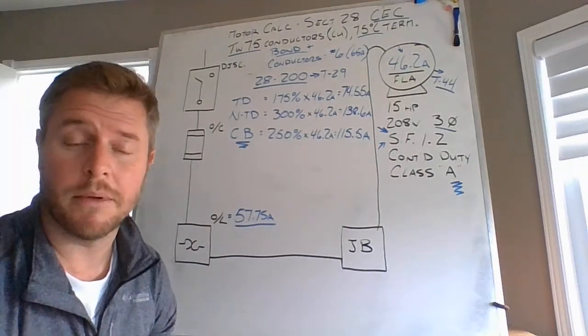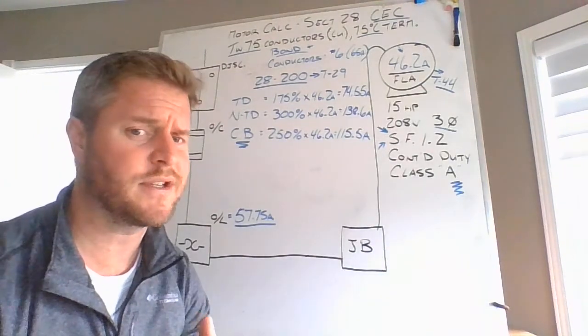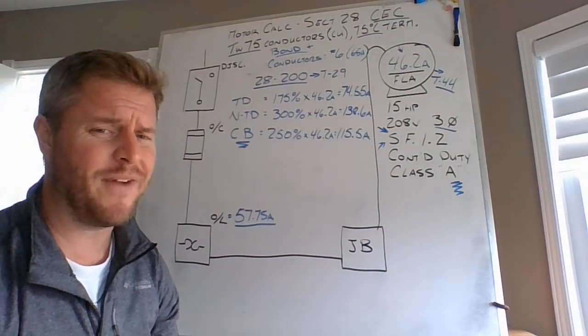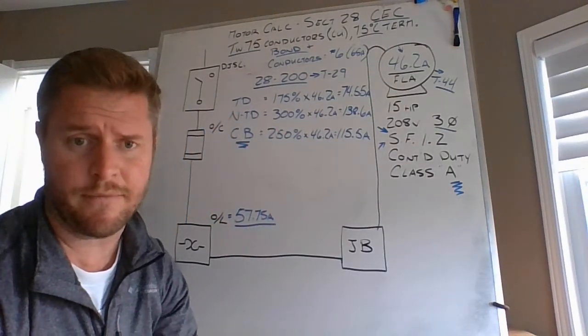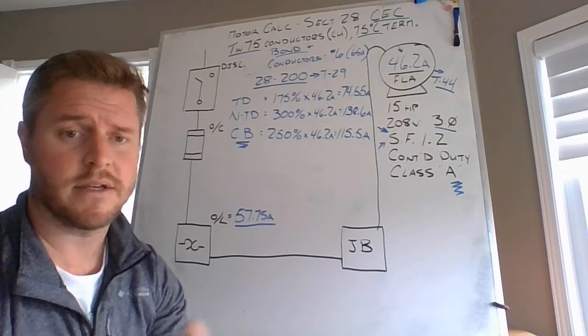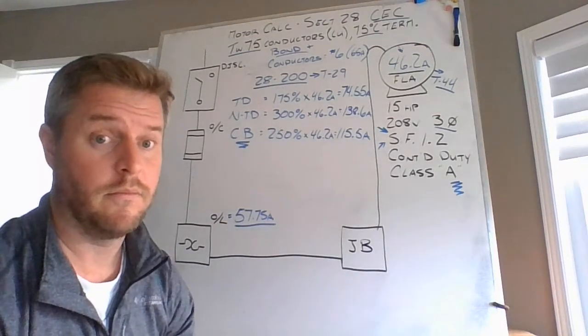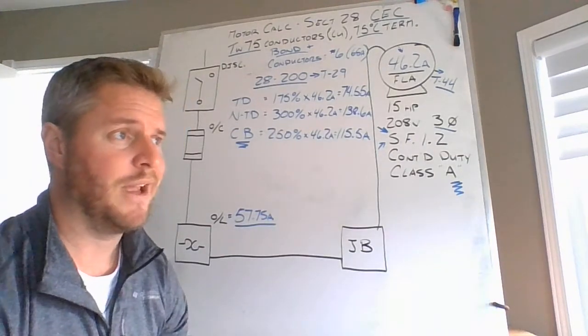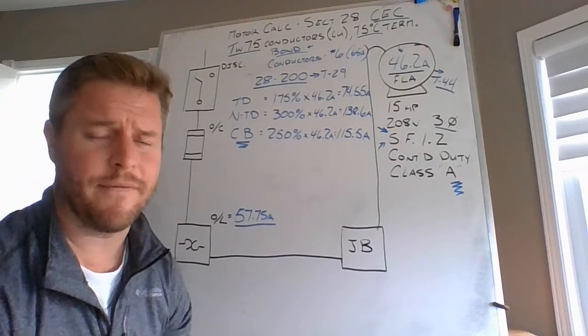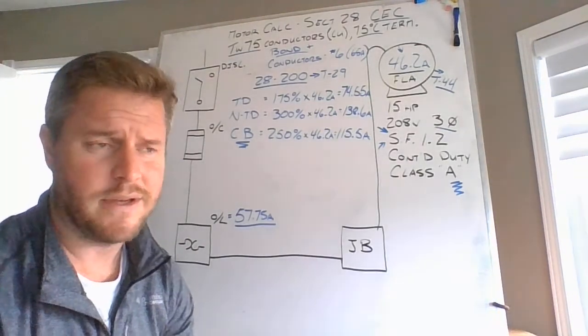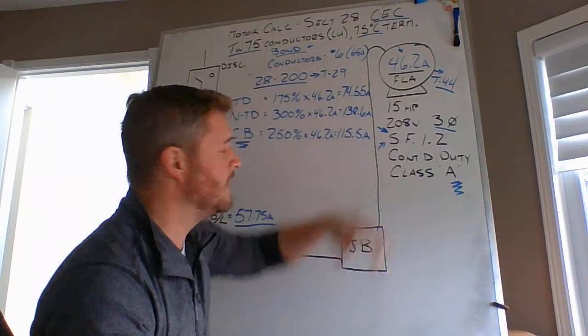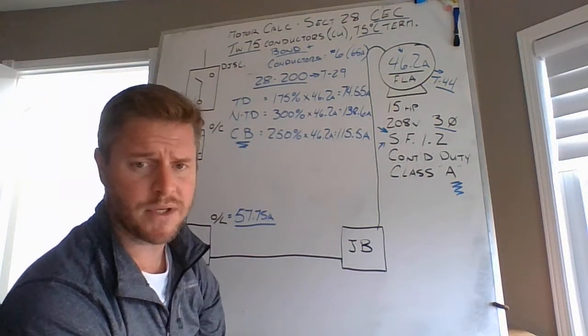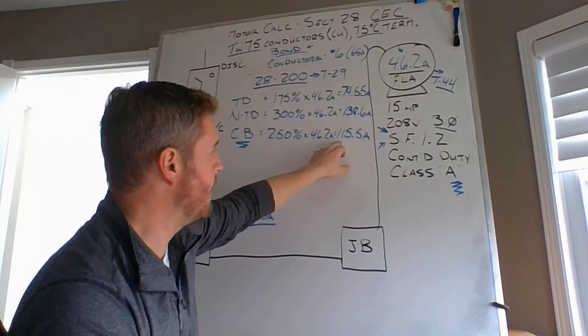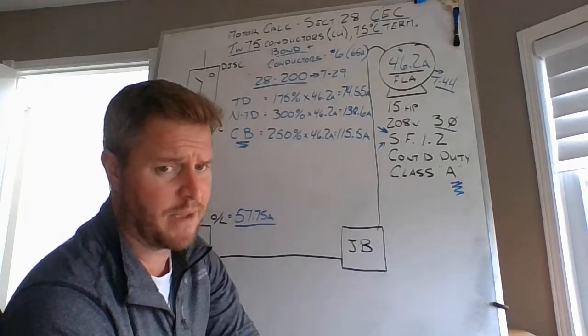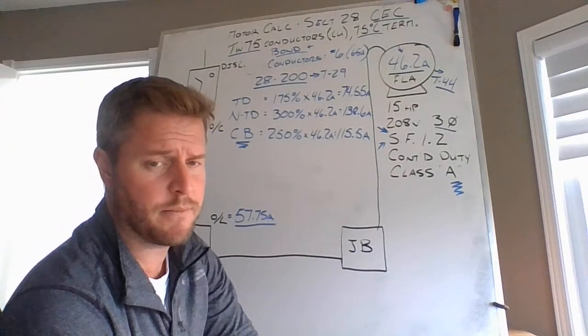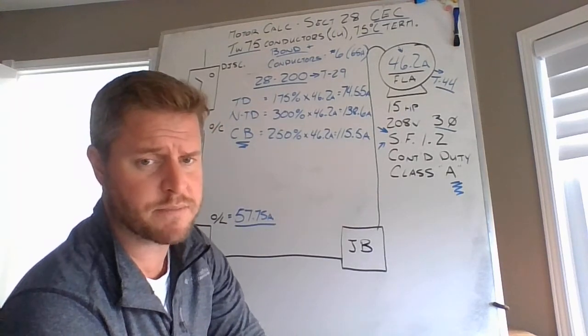They're going to say, no problem. You come in whenever you get a chance. You just swing on by. No big deal. 74.55. Ah, man, I got too many of those. Thank you for coming in for those fuses. They're going to say, see you soon. Hang up the phone. Wonderful. You show up to the wholesaler, and everybody's having a laugh while they're having a coffee because they don't make a 74.55 amp fuse. They don't make a 138.6 amp fuse for a non-time delay option. And you sure as hell can't go to the wholesaler and buy a 115.5 amp circuit breaker to install for the specific motor.